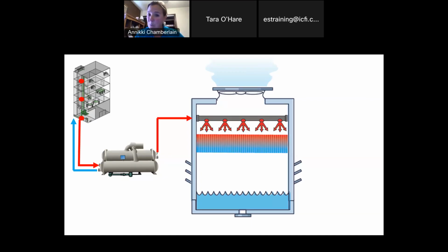We shower that warm, hot water down over what's called fill. You've probably all seen this if you're on this call. This is basically a corrugated material. There are different technologies out there, but basically what we're trying to do is increase the surface area of that water. We've got this big fan going, we've got air pumping through there, we've got hot water, so we're trying to get as much evaporation as we can. By the time the water gets through that fill, it's cooled down quite a bit. Then we send that cool water back to the chiller, ready to pick up heat, and bring it back to the cooling tower to cool it down. So this goes on and on, the loop with the building and the loop in the cooling tower, all to remove heat.